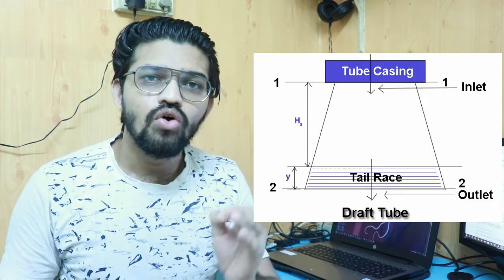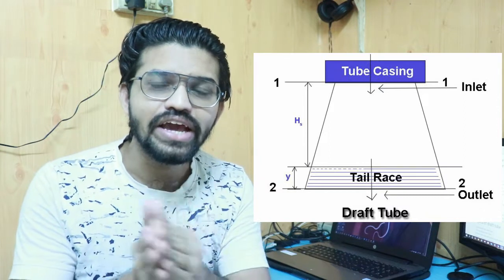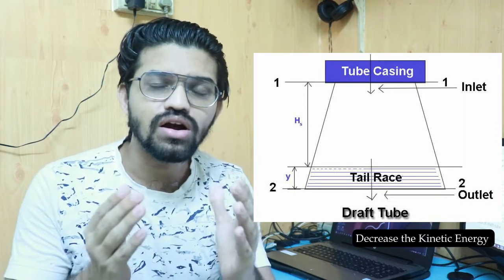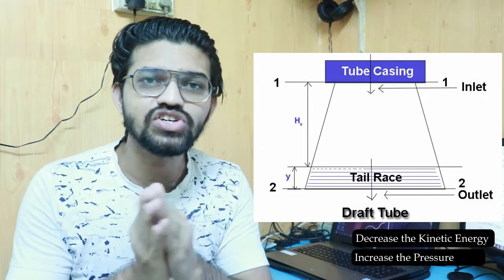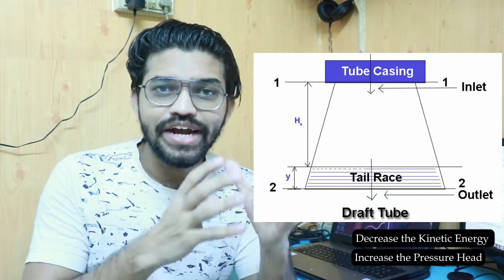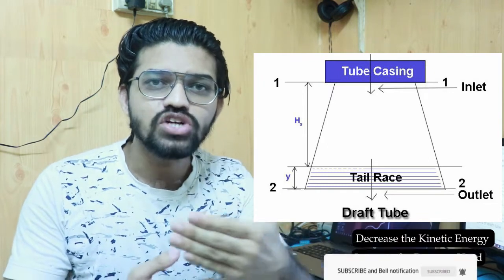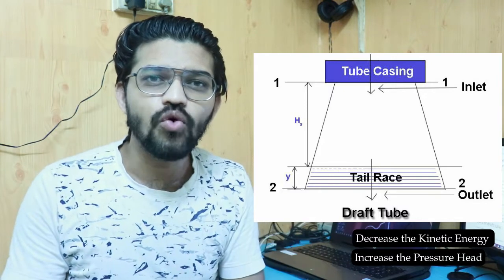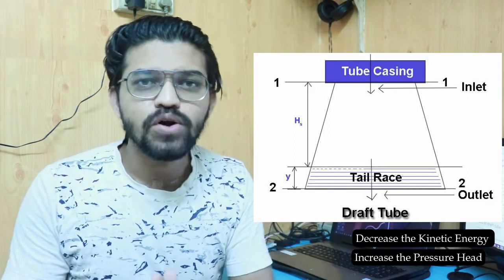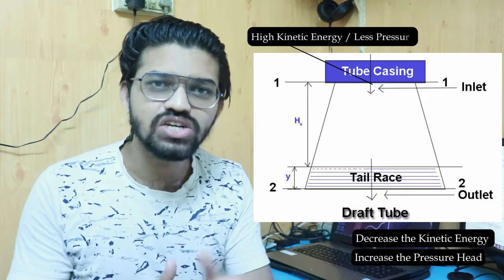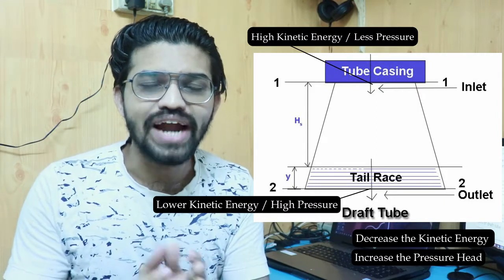When water comes out from the turbine it has higher kinetic energy and lower pressure head. In the draft tube, because of the increasing cross-sectional area, the kinetic energy of the water gets reduced and the pressure head increases. The draft tube converts the kinetic energy of the water into pressure energy — it increases the pressure from section 1 to section 2. Section 1 represents the inlet where water has higher kinetic energy, and at section 2 the water has lower kinetic energy and higher pressure.